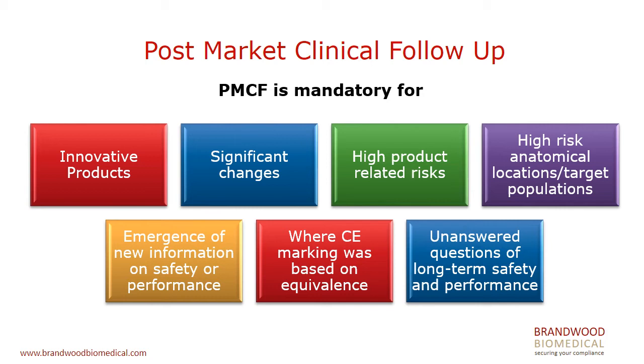If you have not used direct clinical evidence - in other words, if your device doesn't have direct clinical study data supporting it, but instead you've established clinical evidence based on equivalence with other similar devices - then post-market clinical follow-up is mandatory. That's going to raise the requirements for quite a lot of devices, because many of the lower risk devices don't have direct clinical studies, but you are expected to monitor in the post-market how your device works.